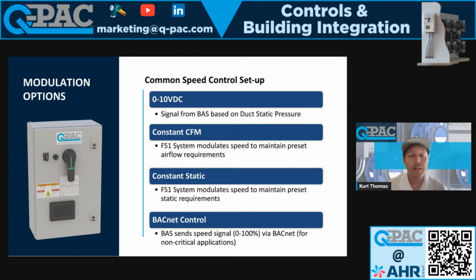And the final way is for BACnet. So I only suggest using BACnet speed control for non-critical applications. Because if your BACnet network does go down, then our fans are going to continue to run at the last speed signal they were given. And then if you have a power cycle, then they won't run at all. So as long as your BACnet network is in good shape, you can send a signal to our fans and we will modulate up and down.